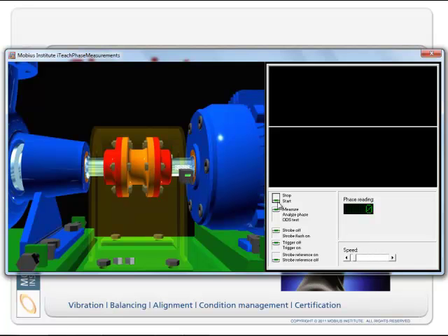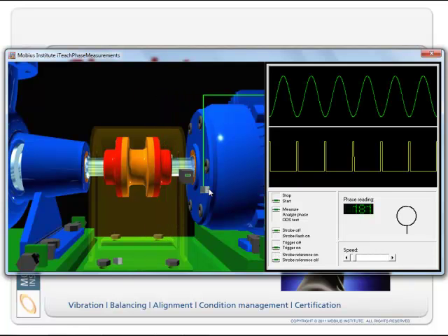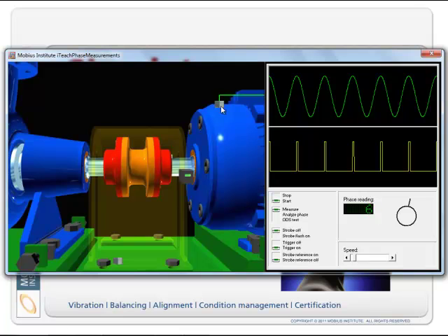And if I was to start the machine now, you see it's spinning. You can't really see the bolts because it's just blurred. And there's my once per revolution tachometer signal. What I can do is turn on triggering, so now the analyzer locks in and keeps that nice and steady. Now with this vibration sensor, which you can see is connected to the top waveform display, here is the vibration just at the running speed, we know because we've got this tachometer here. So this is the vibration, and because it's one frequency, it's a sine wave.